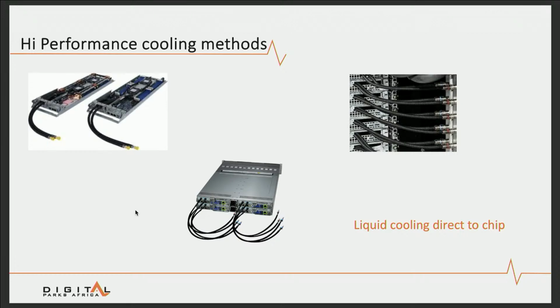It requires very high water pressures to be able to circulate sufficient water flow right through the heat transfer plate on the chip. And the cooling water itself causes certain chemical reactions, degradations, more on the connector side. So it's a technology that requires lots of regular servicing and maintenance, where the different couplers are engaged onto the chassis. So quite an intense technology to maintain.